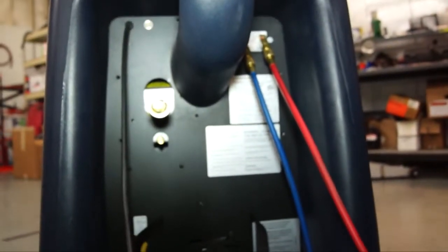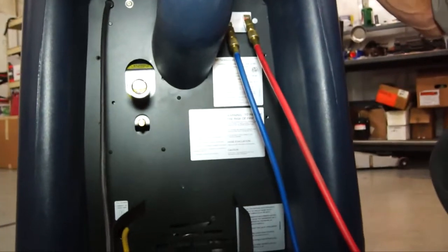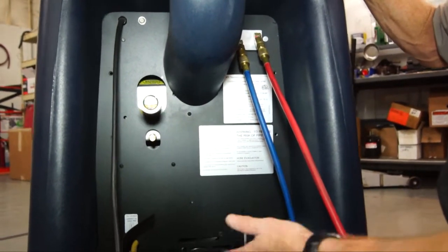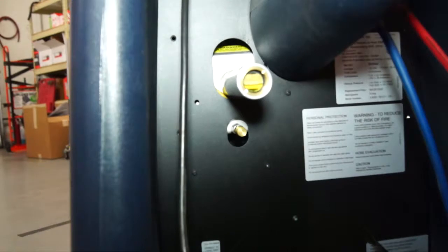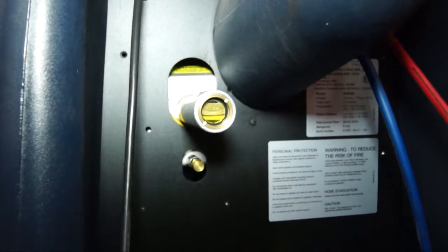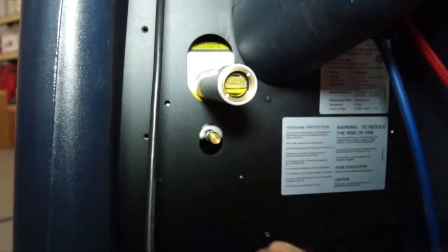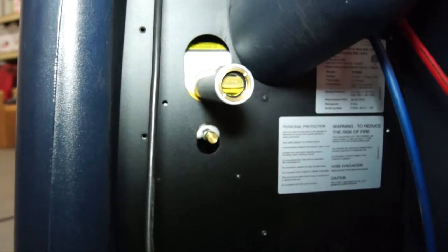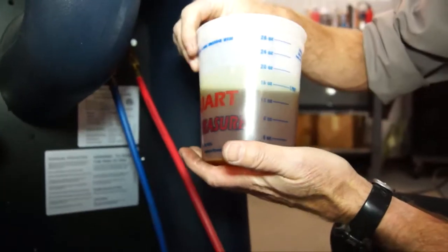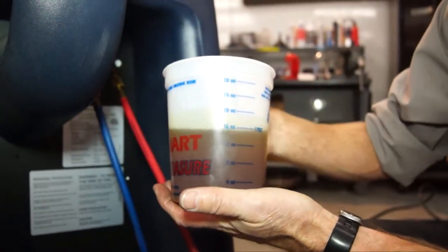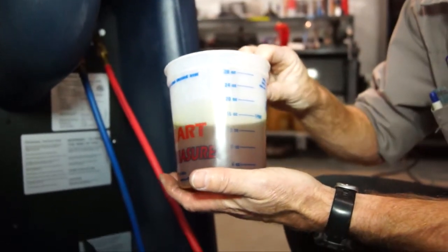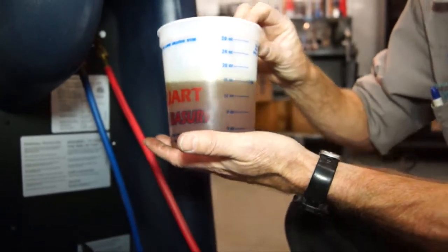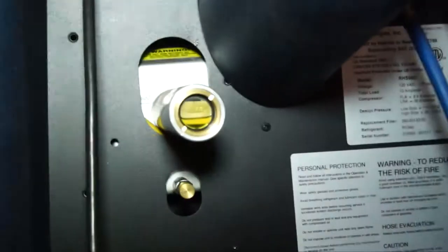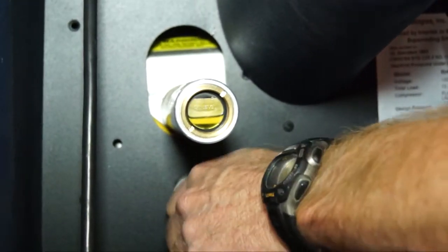So after I get those filters replaced, by that time, my vacuum pump oil has completely drained out. It stopped draining. So I'm going to close the drain port. The oil's pretty dark. I took out about 16 ounces of oil. So that's what's going to need to go back in this thing, give or take a little bit of oil, okay? There's almost 16 ounces of oil in this thing. So again, you want to close the drain port, and now I'm going to fill it up.